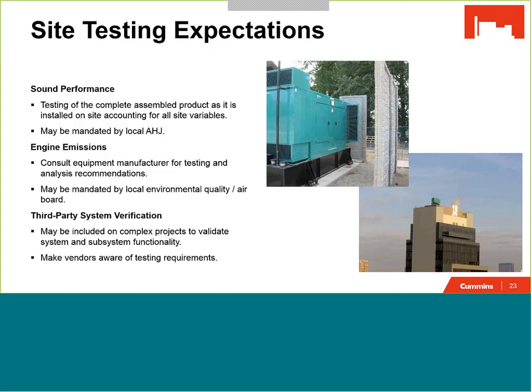Definitely consult with the equipment manufacturer and any other needed vendors, such as test laboratories that may be needed to conduct this testing. Third parties are sometimes brought in additionally for on-site testing and commissioning in order to validate or be there as a neutral party to verify the product performance. Typically we don't see these on small projects, but on large projects with complex systems, bringing in a third party to validate the entire power system performance may be a recommendation. It is important to note that if this is going to be a requirement, it should be clearly communicated to all vendors involved, as this type of testing and verification can have extensive time requirements as well as cost associated with it.